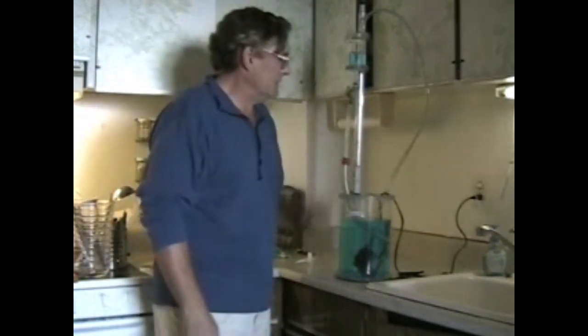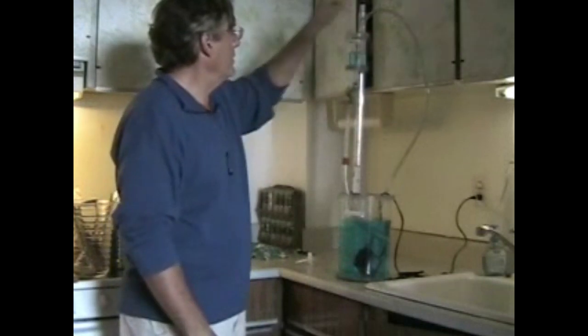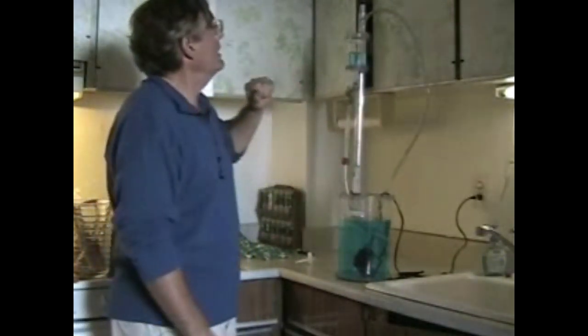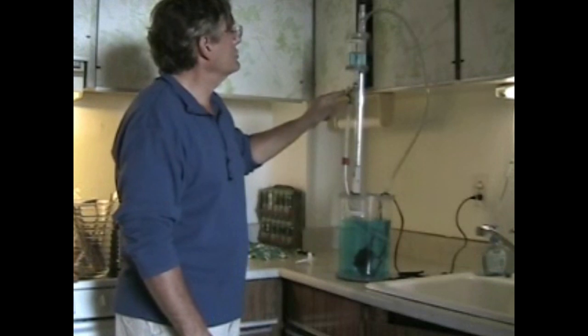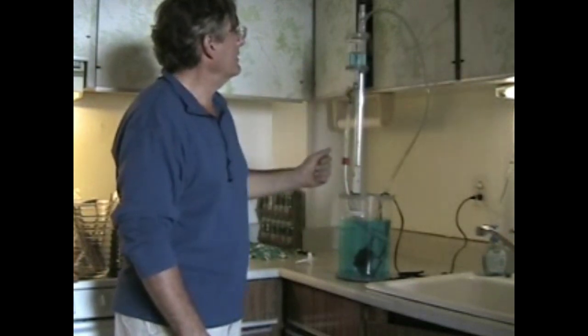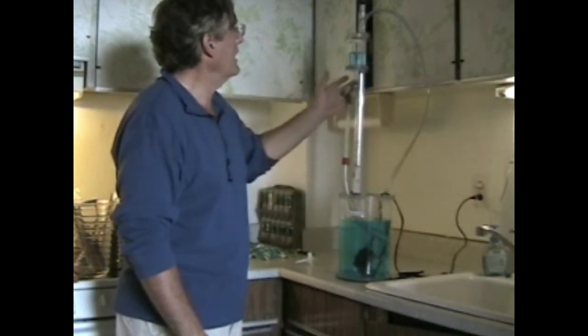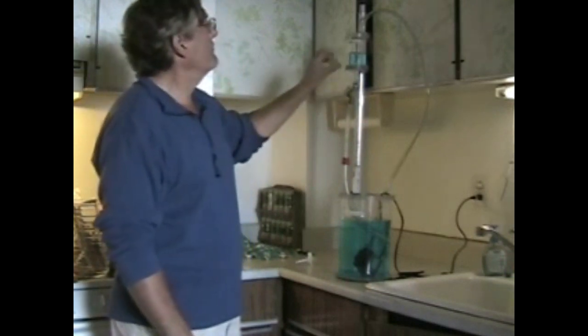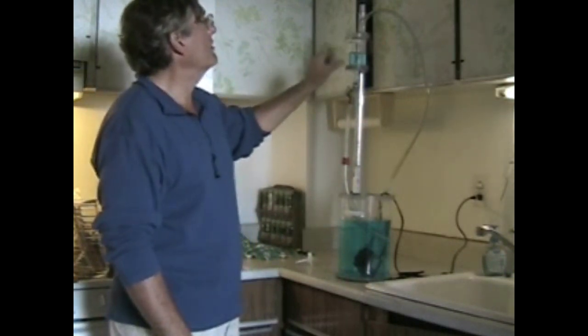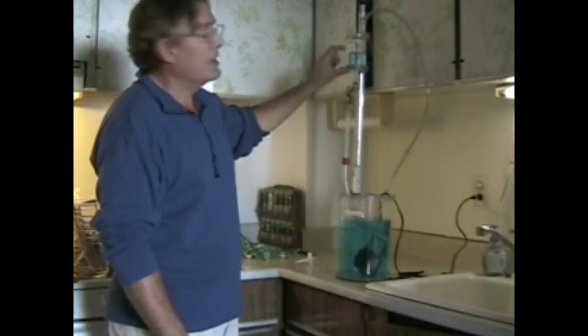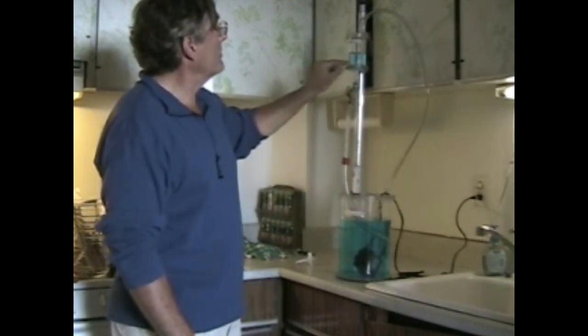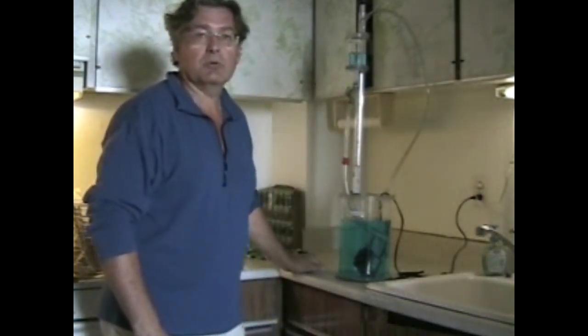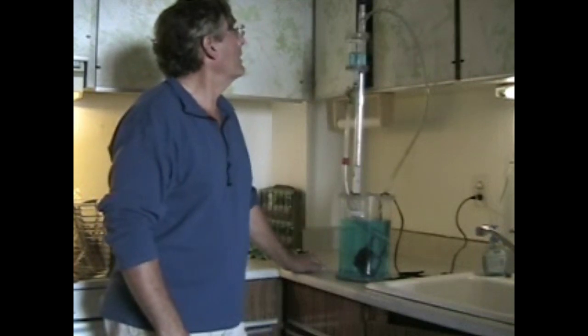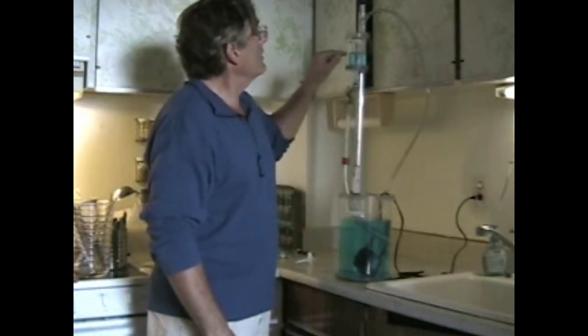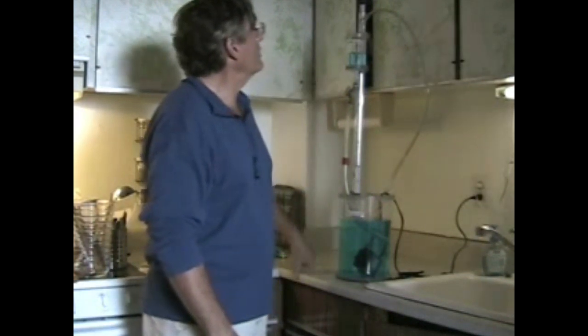What you're seeing here now is the same pump system with a little centrifugal pump running in a recirculation mode. With this discharge valve here on the upper tank emptying side, I can vary the height of the liquid in this upper reservoir. And the smaller I make this height with respect to the connector, which would be similar to a suction pump connection, vortexes will form. I don't know if you can see at this point, we're at a level where vortexes are just wanting to form.